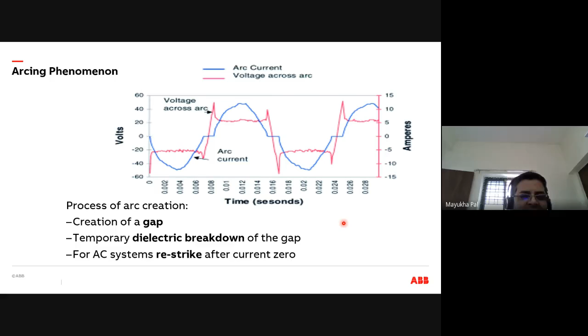So again, we need to detect these. We have well-established mechanisms to detect arc. Line to neutral arc generally will be of high magnitude. For residential applications, the average fault current will be something like 300 amps. This is typically for a 15 ampere AFCI or a 20 ampere AFCI. This will be the typical fault current. Then you will have patterns that you have to find out for arc, and keep them. And then you have to use that pattern to detect whether it's an arc or not an arc.